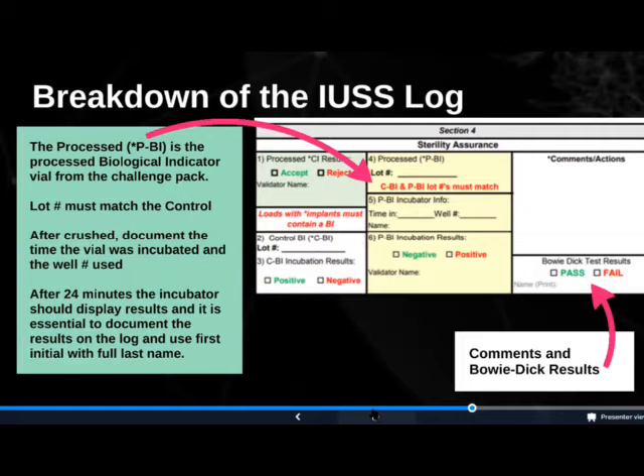After it's crushed, document the time the vial was incubated and the well number used. After 24 minutes, the incubator should display results. It'll have a plus sign for positive or a negative sign for negative. And it is essential to document the results on the log and to use your first initial and your full last name. Now, here we're looking for it to be negative. We want to know that there is no live spores in that vial, because the steam sterilization did penetrate the instrumentation, and so we feel confident that the patient will be okay.